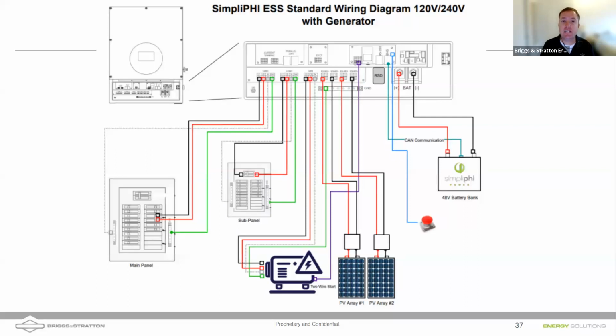And that's the key to this talk here: we can use a 2-wire signal to start that generator. The inverter knows the state of charge of the batteries because they're communicating together, and it can then use the state of charge of the battery to start that generator when the batteries are starting to get low. Start up the generator, charge up the batteries, top them off, and then shut the generator off as well.